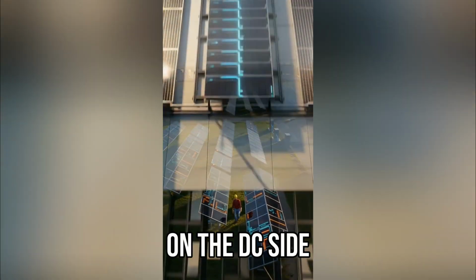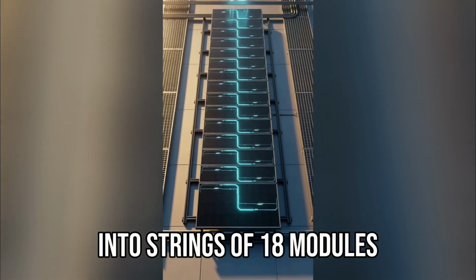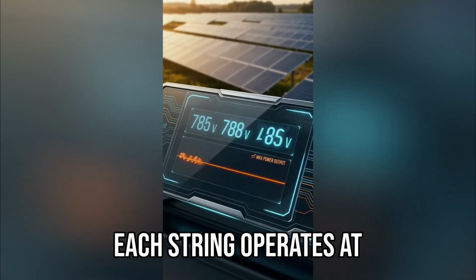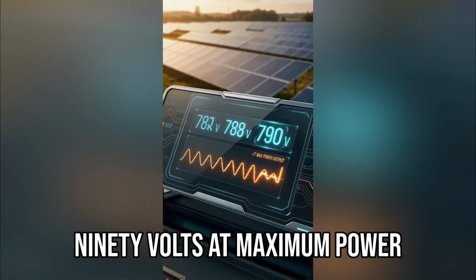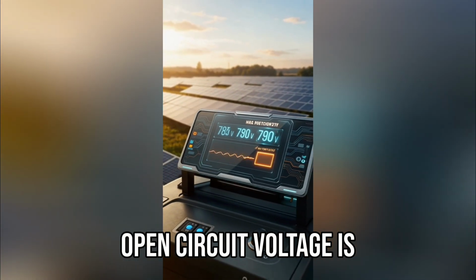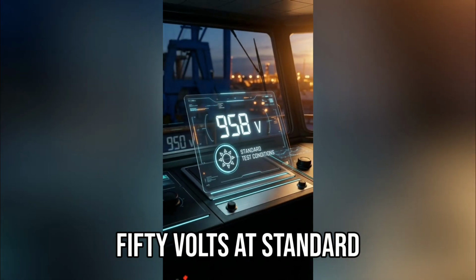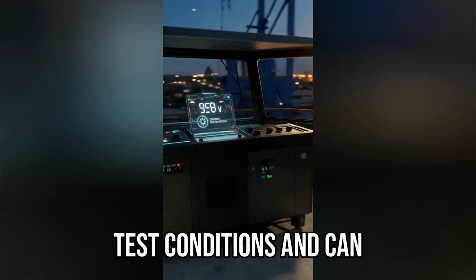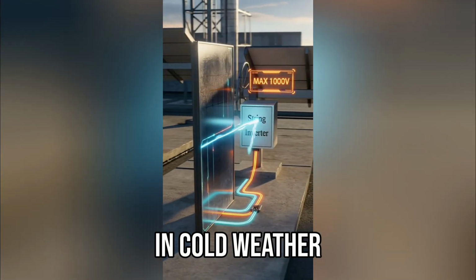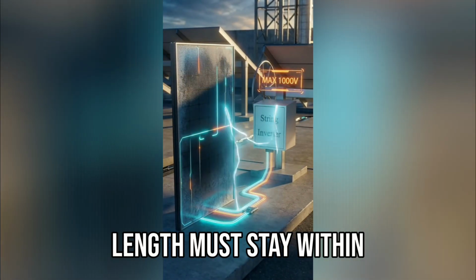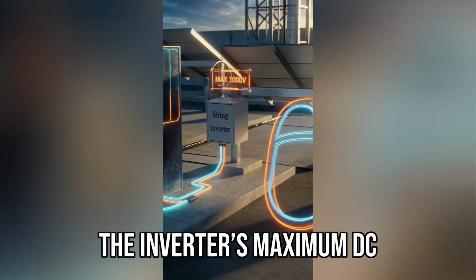On the DC side, the array is divided into strings of 18 modules. Each string operates at roughly 790 volts at maximum power. Open circuit voltage is about 950 volts at standard test conditions and can exceed 1000 volts in cold weather, which is why string length must stay within the inverter's maximum DC voltage rating.